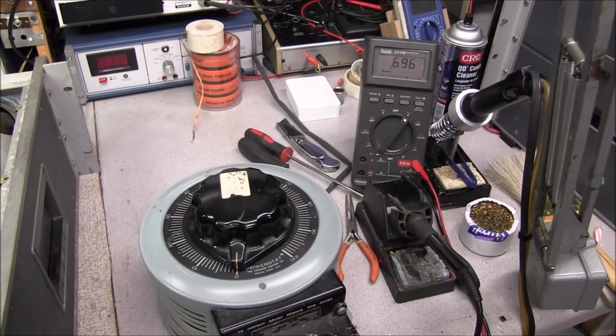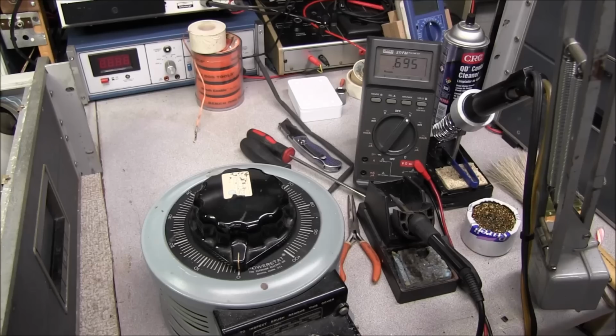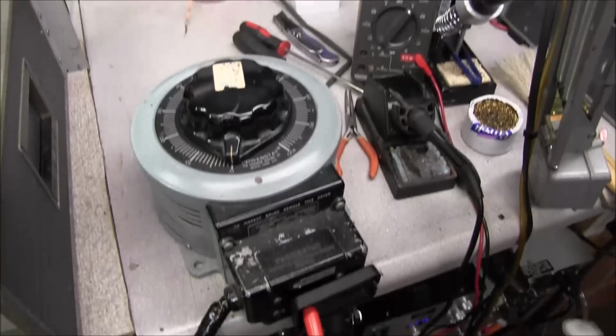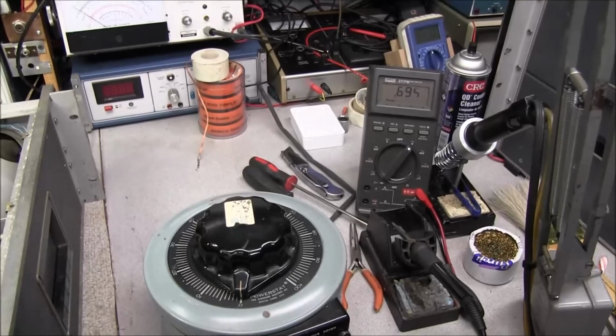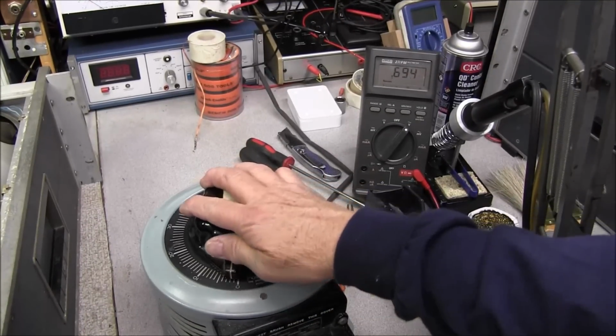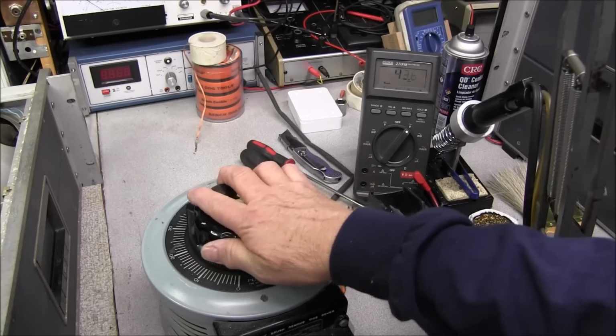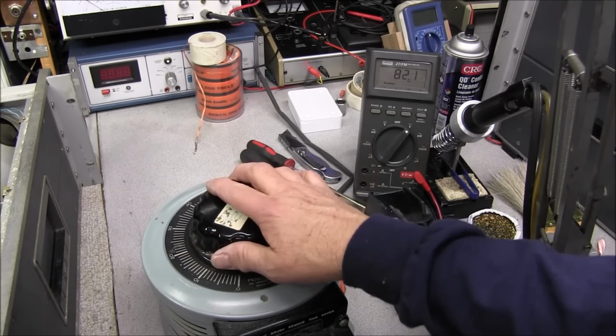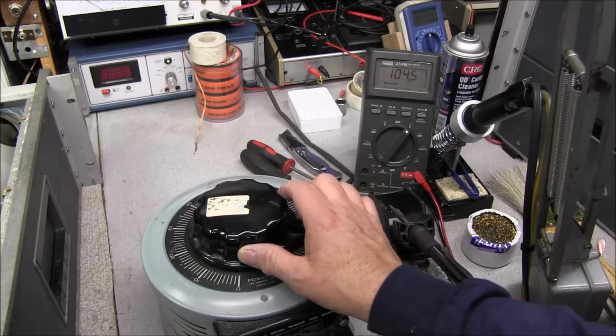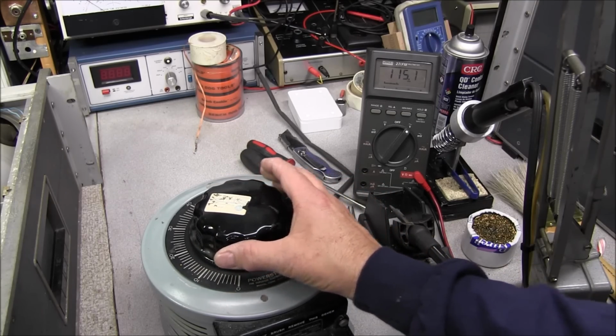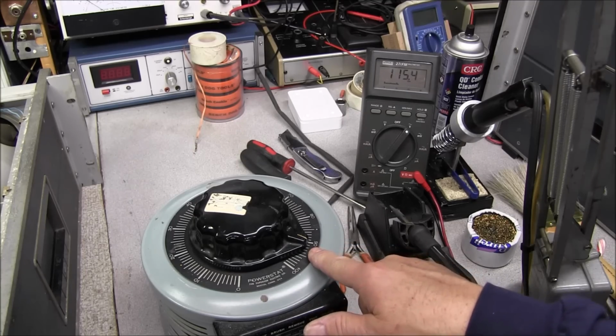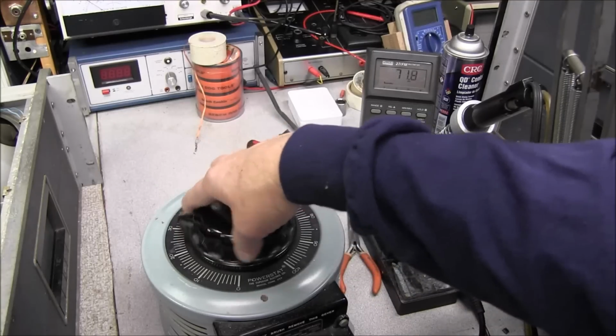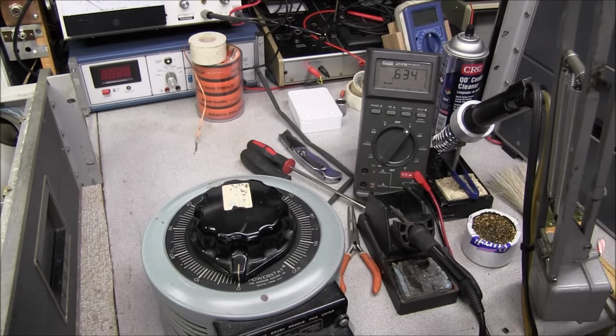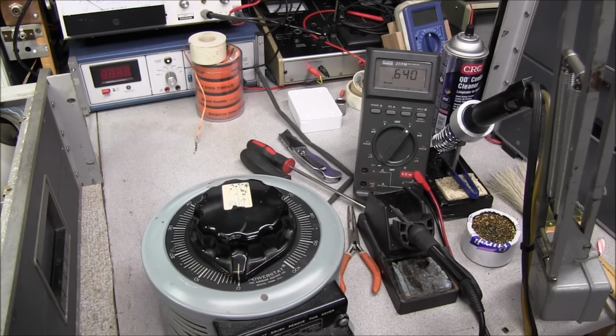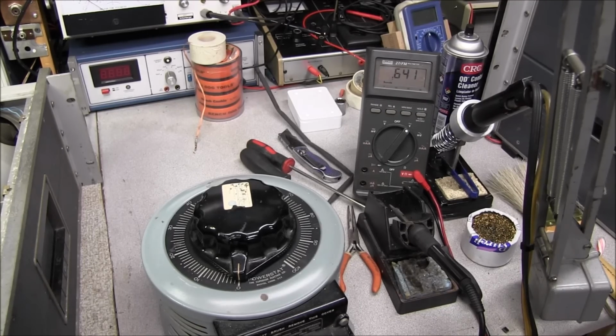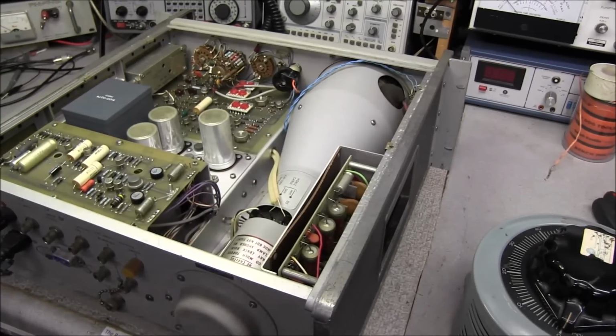I have my variac set up, and if you noticed, I have the line cord plugged in with the voltmeter on it. I want to bring the variac up and see where 115 volts is today, because I really don't want to go much past 115 volts on this piece of equipment. It looks like it's on about 82. It's going to be 115 volts, so I can turn that back down to 0. We're going to plug the unit in and bring it up on the variac real slowly just to see if we have anything.